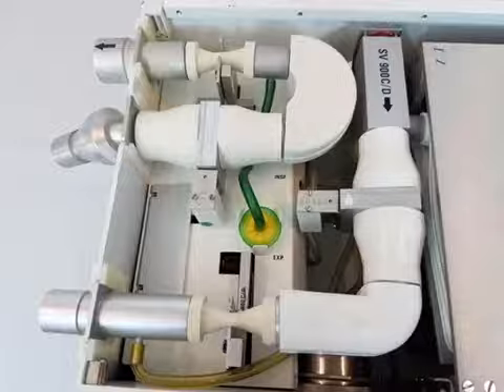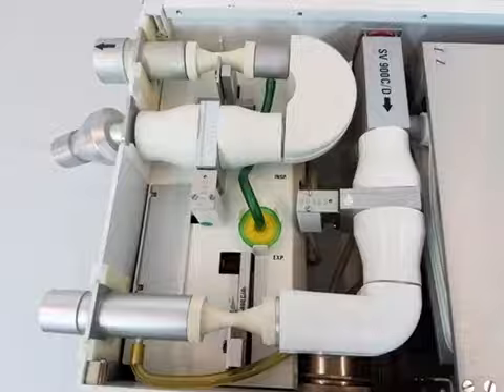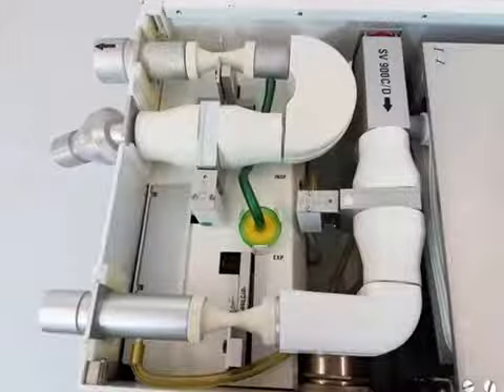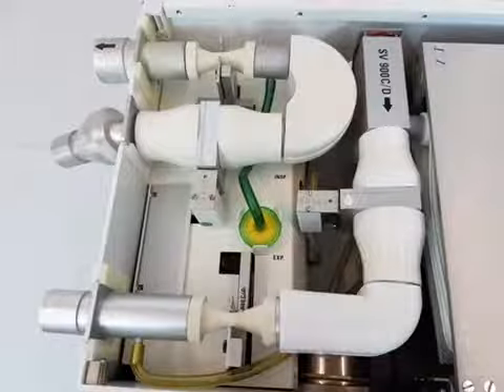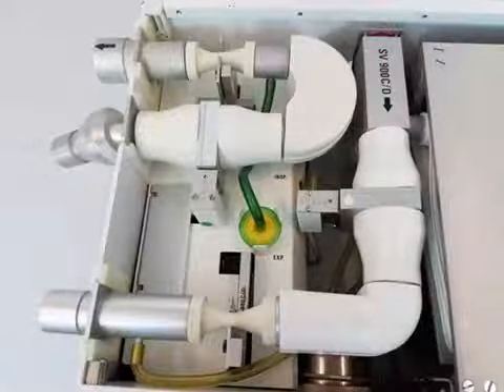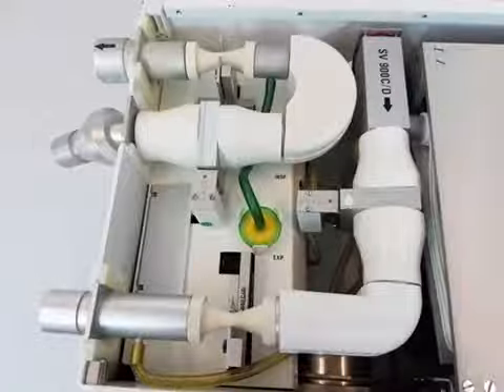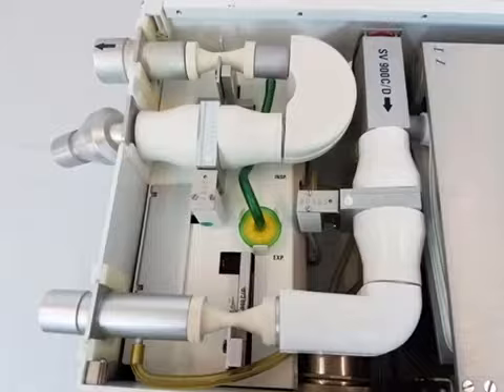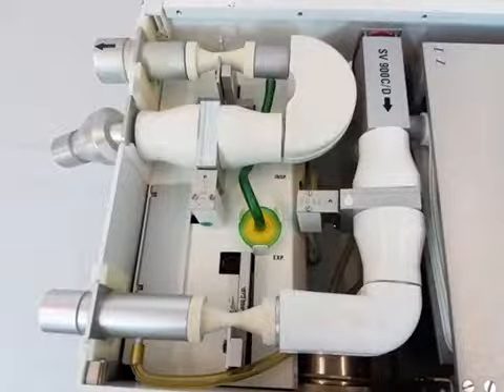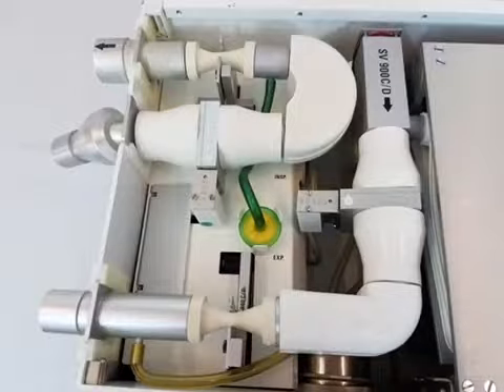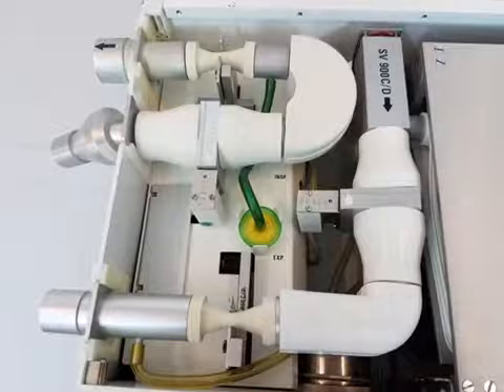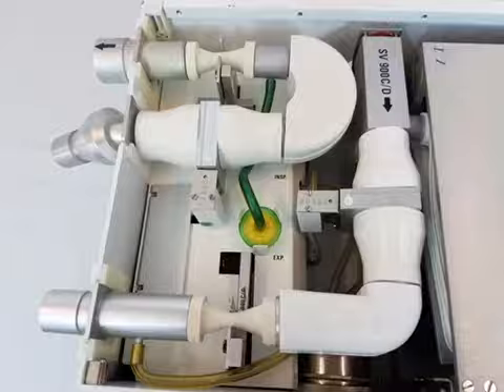Now the gas curves around, it comes down to here. This is my inspiratory valve, or some people call it the inspiratory scissor valve because it looks like it scissors when it opens and closes. That regulates the inspiratory gas flow. It's closed during the pause and the expiratory parts of the respiratory cycle. And up here where you see inspiratory, down there, where I'm shooting with my laser pointer, is the pressure transducer for the inspiratory side, and it measures my airway pressure.